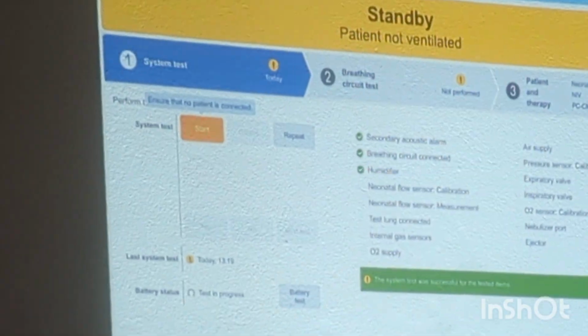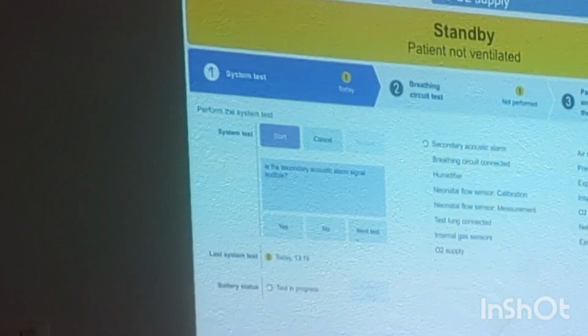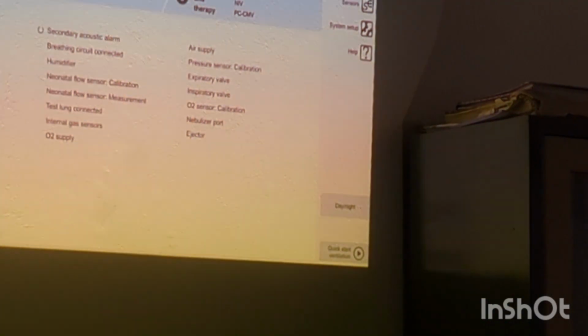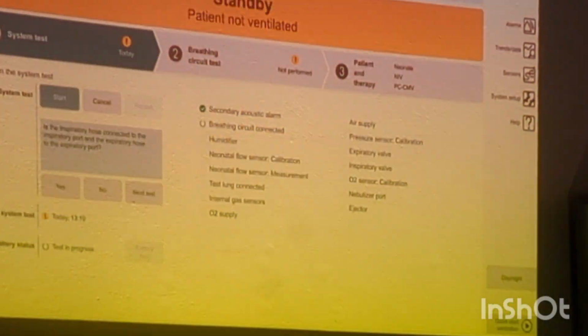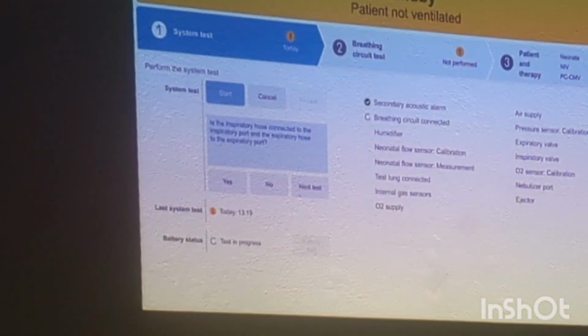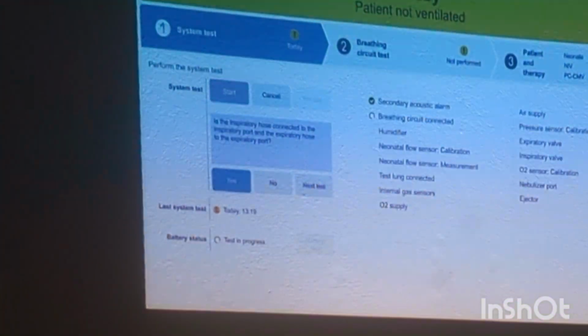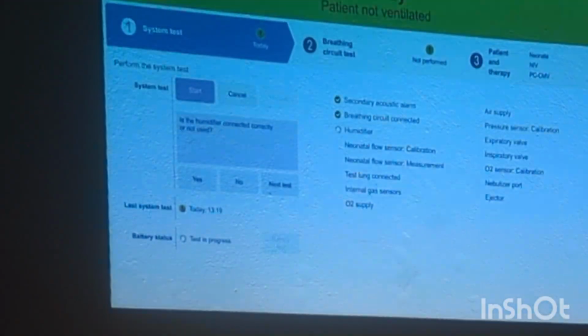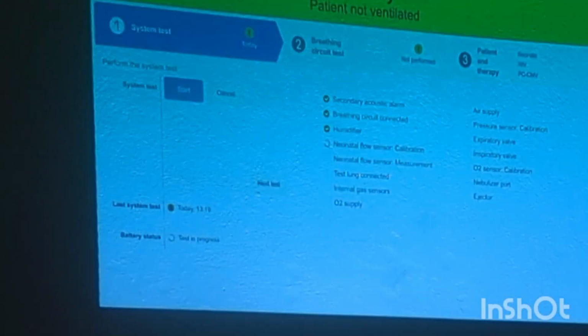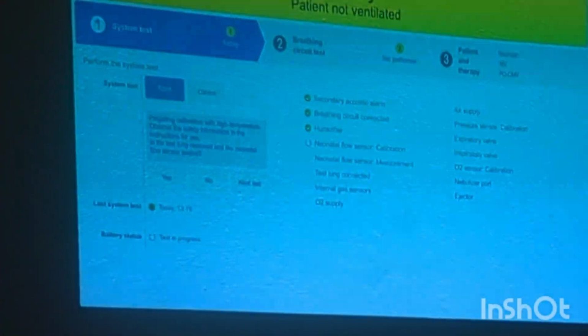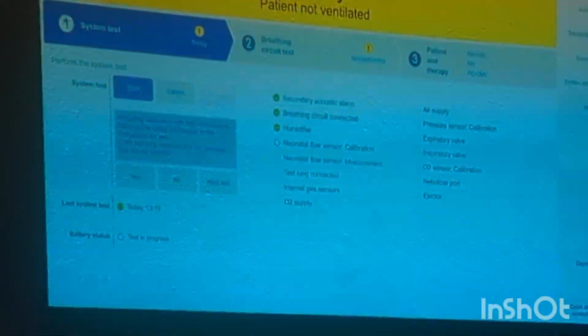So see, once you start, first it will ask you for the secondary acoustic. This is a safety acoustic alarm. You can hear this alarm sound, then you can confirm. You have to select yes. Then it asks if the inspiratory hose and expiratory hose are connected. Here the machine is not testing anything, it is just confirming, so you have to confirm. Again it is a question for you. If you say no, the message is that it is partially completed.